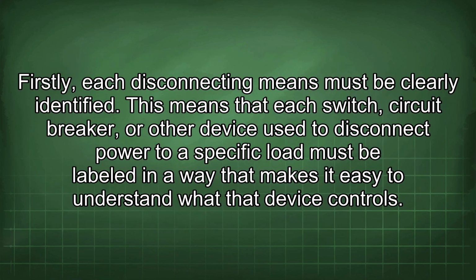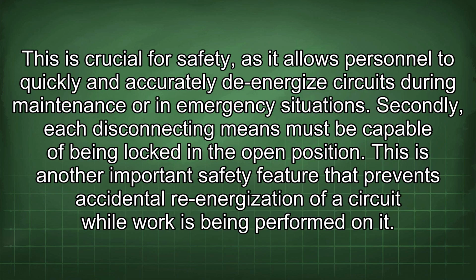Firstly, each disconnecting means must be clearly identified. This means that each switch, circuit breaker, or other device used to disconnect power to a specific load must be labeled in a way that makes it easy to understand what the device controls.